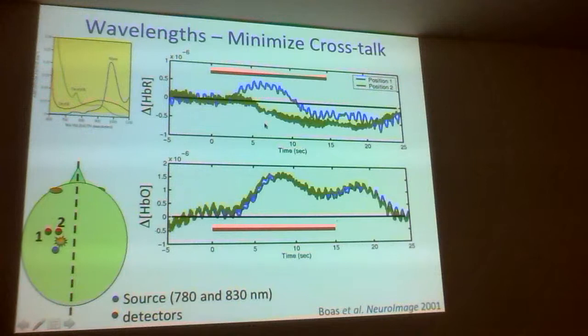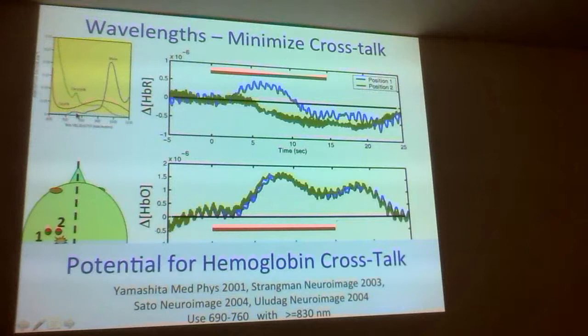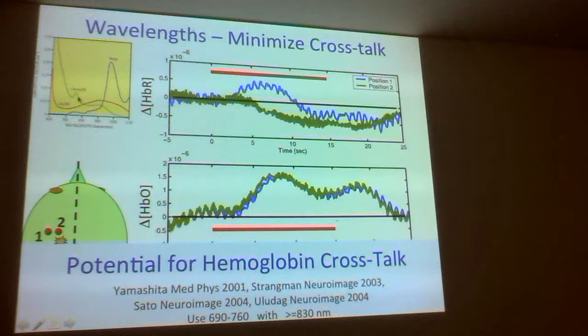The only way to reduce that crosstalk effect is to change your wavelengths — you had to use wavelengths with a bigger difference in the extinction coefficients of oxy- and deoxyhemoglobin. We did the theoretical analysis and suggested using 690 nanometers with 830 nanometers. Several other people did the same analysis and suggested the same thing. Now most commercial systems are using those wavelength pairs. You could also use 750 nm with 830 nm, but laser diodes at 750 are not as common as at 690.